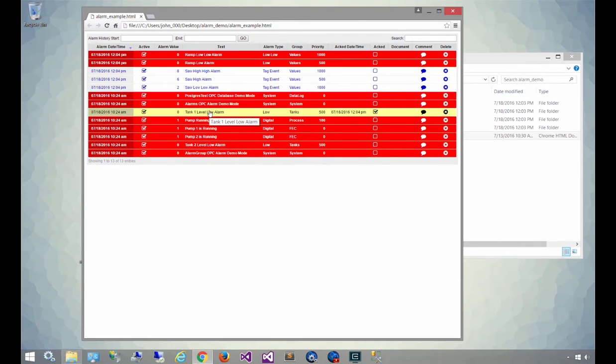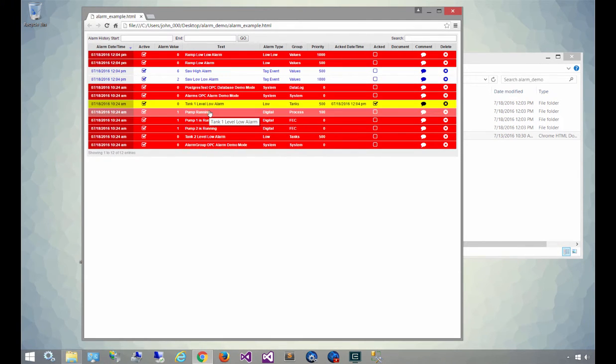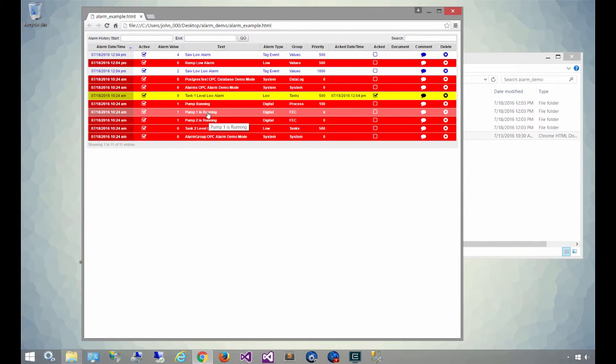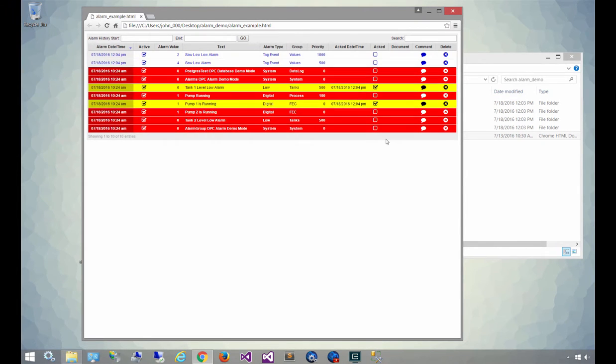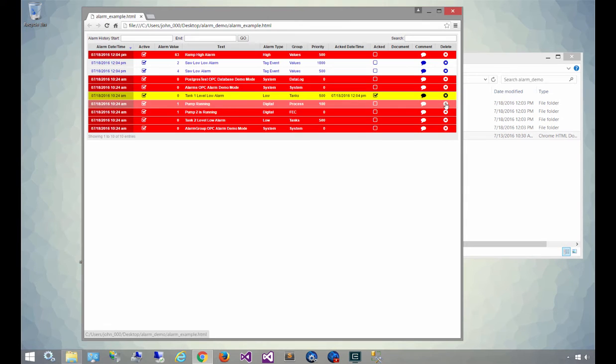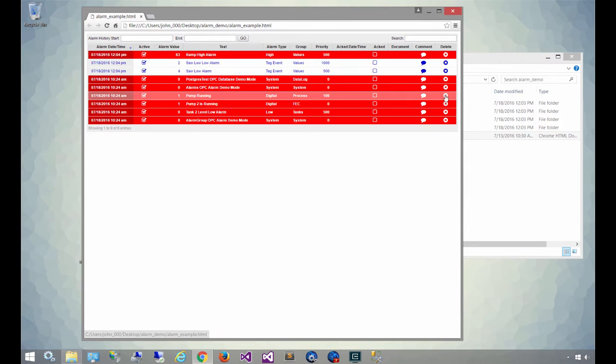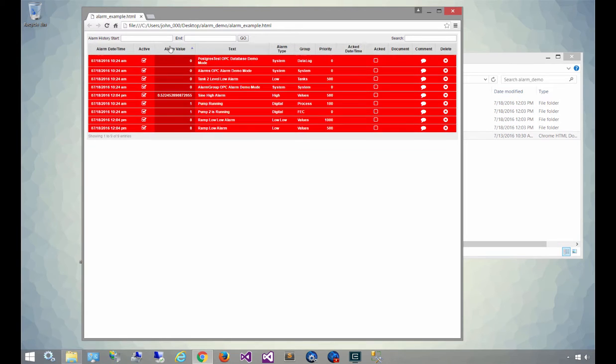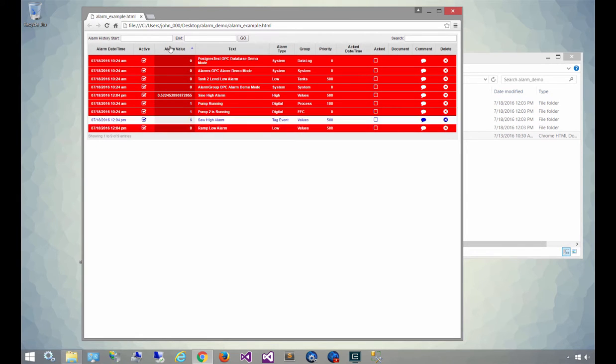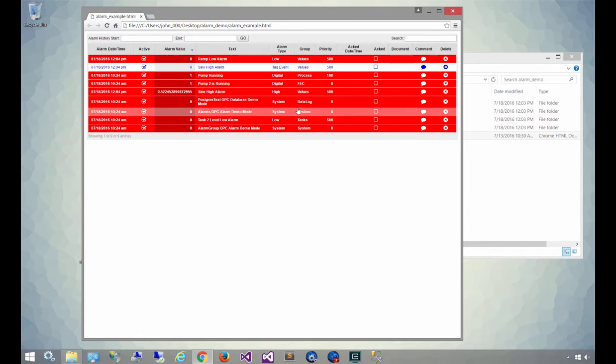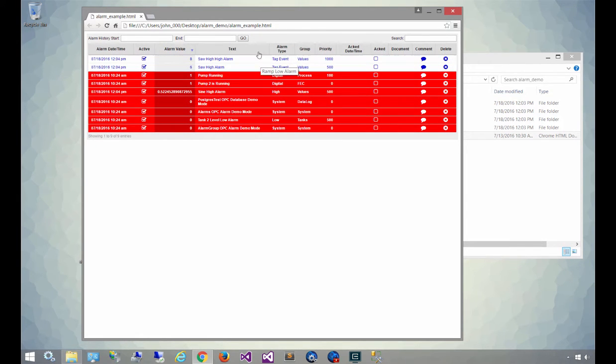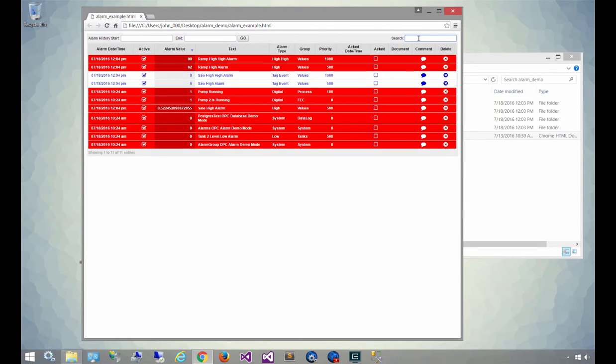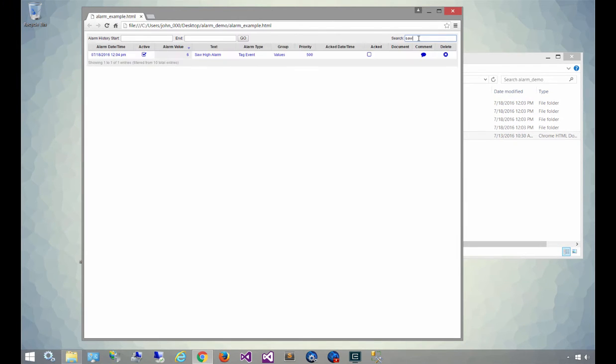WebAlarm is fully interactive, so you can even double click on any of the alarms to acknowledge them. That sends a signal up to the server to mark them as acknowledged. And by default, the delete column is enabled, so that you can just click on the X to delete an alarm. And next to it, there's a comment column so that you can click on that and add a comment on an alarm. So now that we've seen it in action, let's open up the source code and see how it all works.